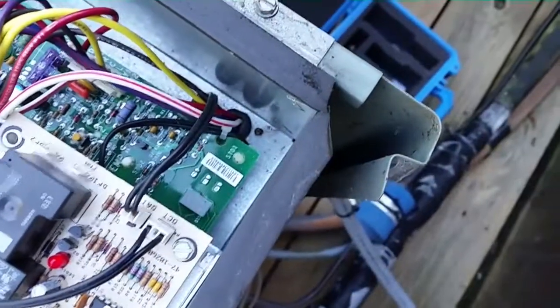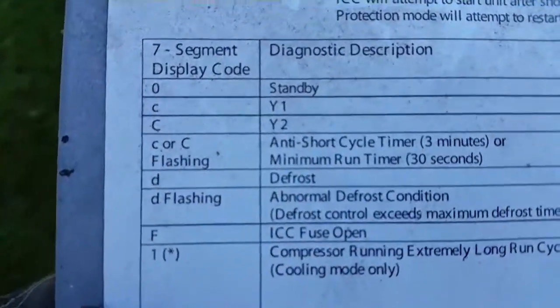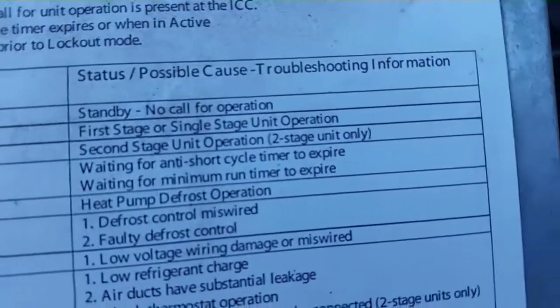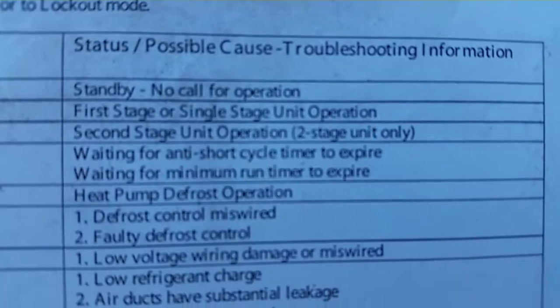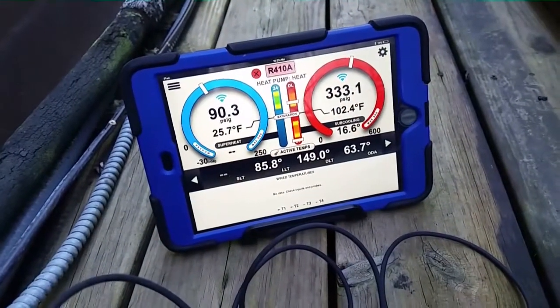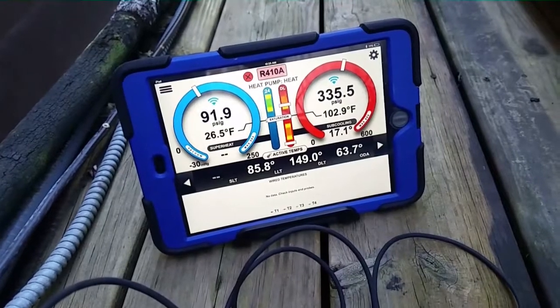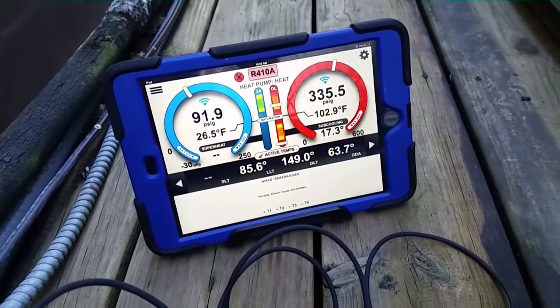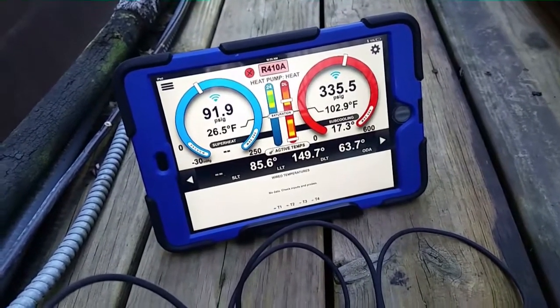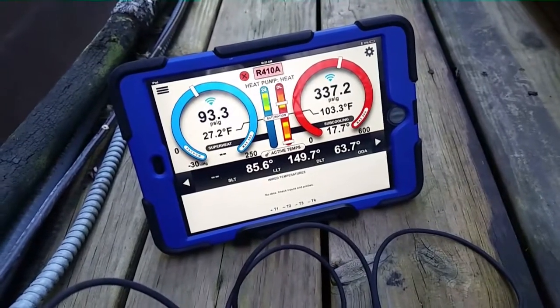You see on the Rheem we have a C flashing. Our C flashing is an anti-short cycle timer. The solution is to wait for the timer to be done. Got the Bryant here, 333/90. It's coming back up now. It just started a second ago, so it's going to rise back up. We have our discharge line temperature 149. Outdoor air 63 this morning. It's warmed up a little bit.